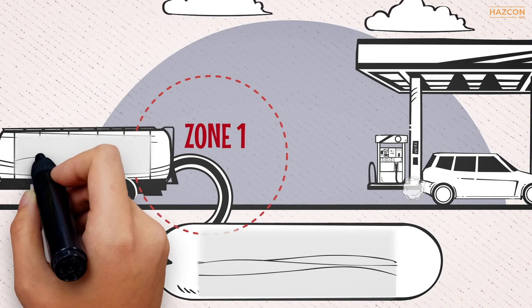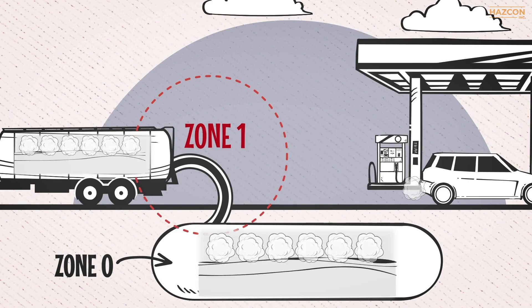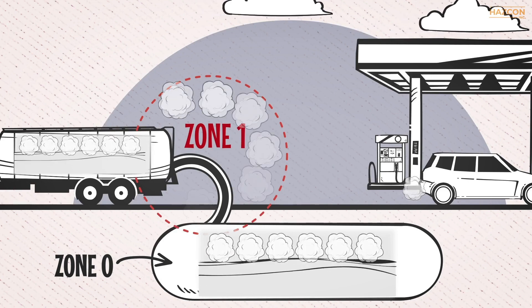In this illustration, we have a storage tank which contains a flammable liquid. When the flammable liquid is being transferred, the area around the vent of the tank is Zone 1.